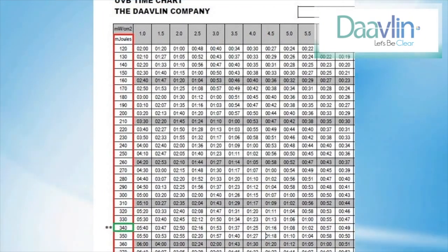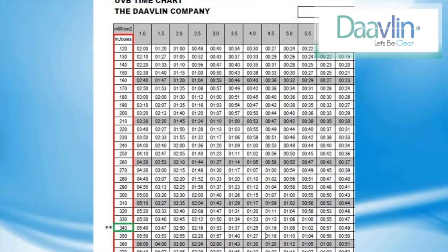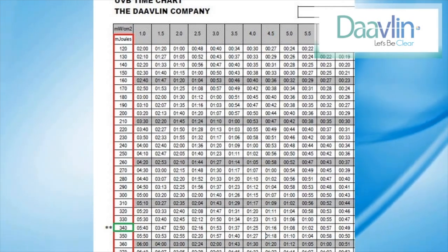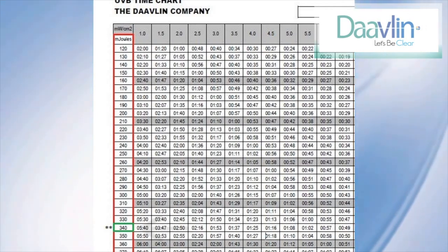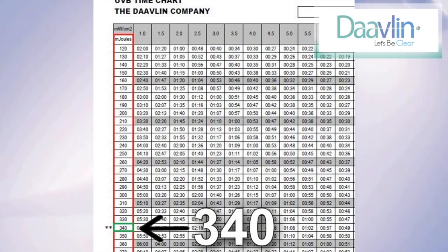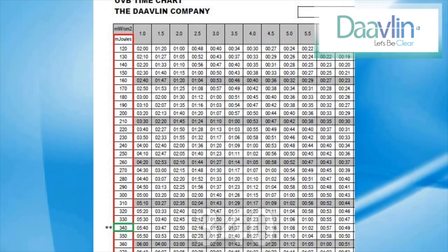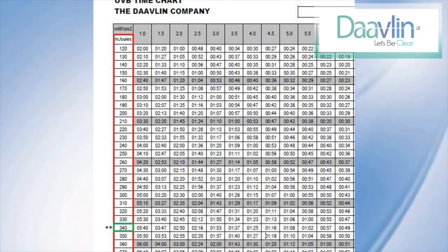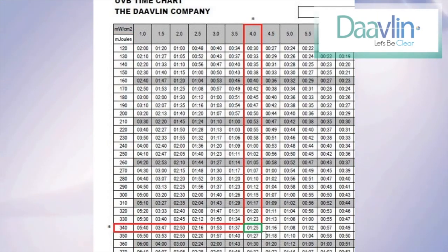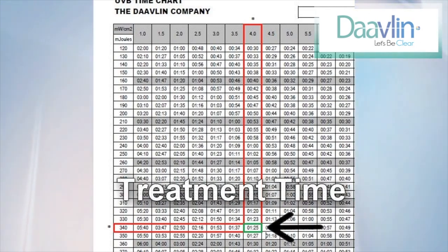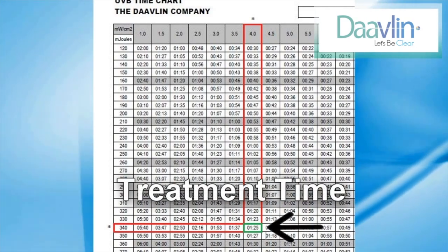Next, look at the column on the far left. Here you will find a wide range of potential doses. In our example, the prescribed dose is 340 millijoules, so we look at the column and find 340. Now, to calculate the treatment time, we need to find where the power output and the prescribed dosage intersect. This intersection will be the treatment time.